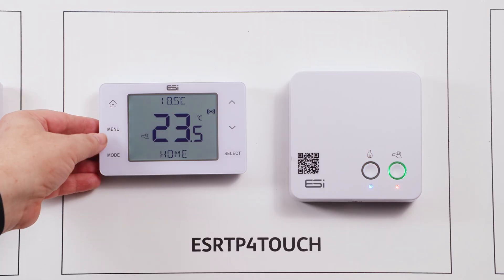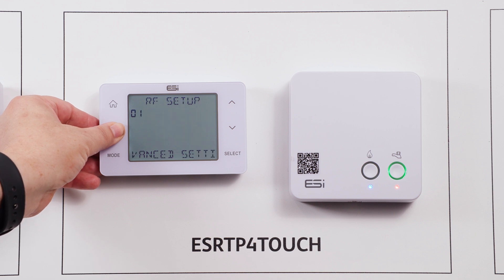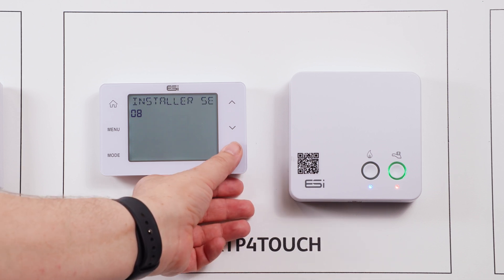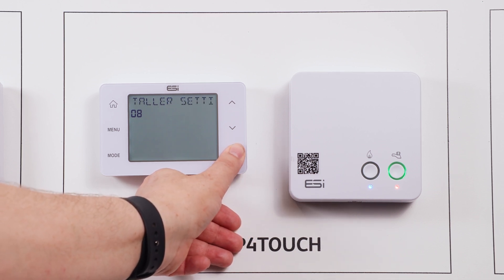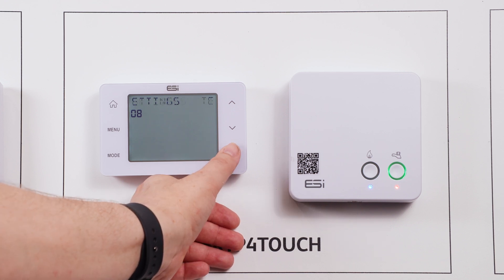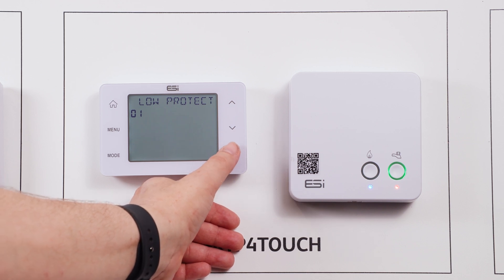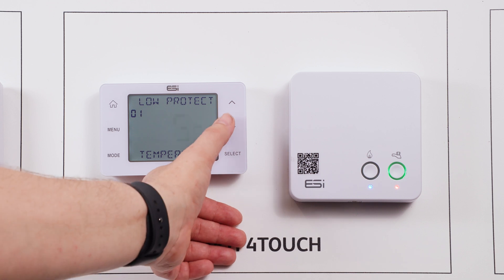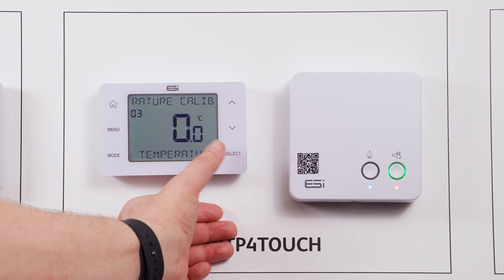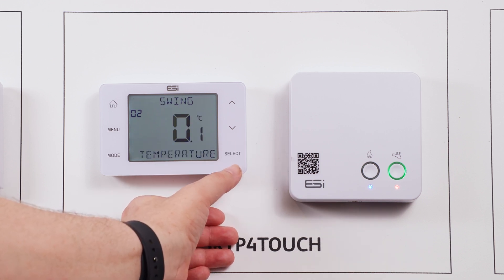To enter the technical menu, first wake up the thermostat then hold down the menu button until you see RF setup on the screen. Press the down arrow once until you see installer settings and hold select until installer settings becomes technical settings. Here you are in the technical settings mode. Within this menu you will have access to settings such as low protection setpoint, TPI, and landlord service interval reminders. For more information, please refer to the manuals provided.